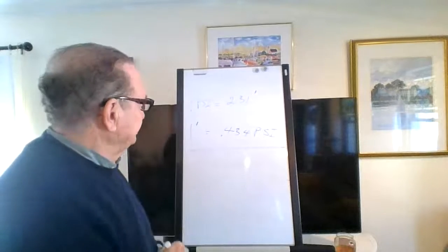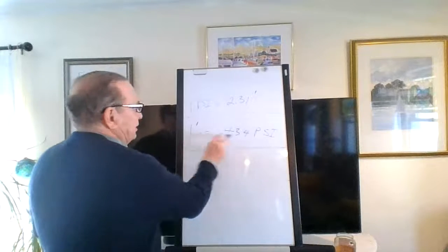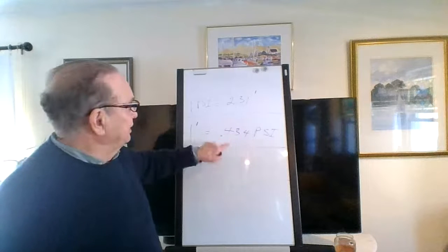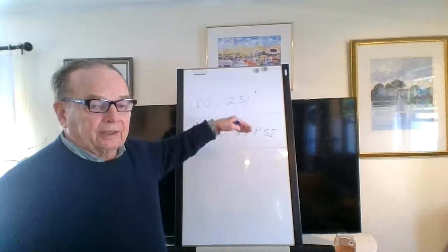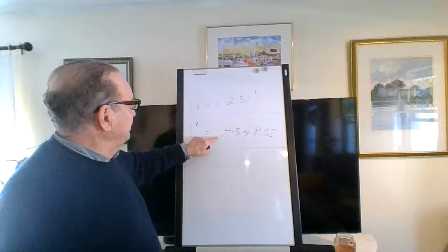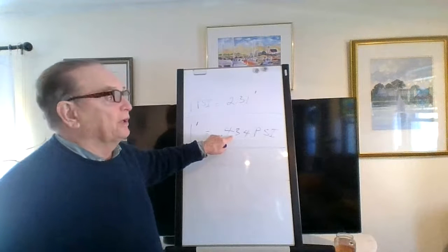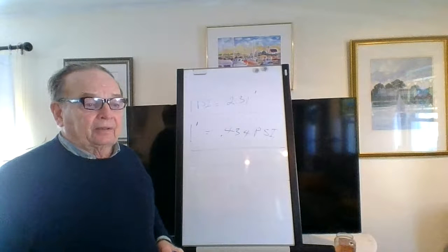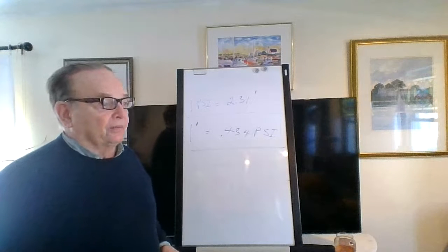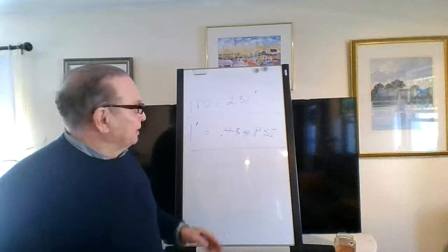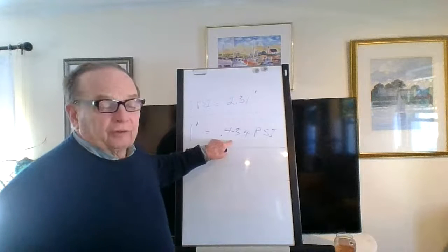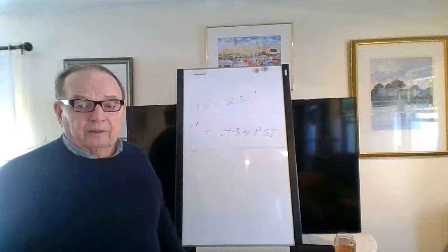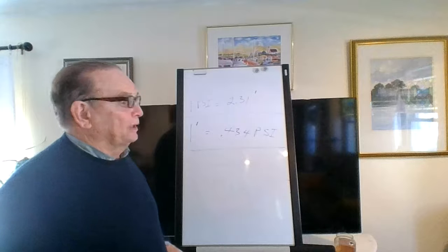Well, let's check. Every foot is 0.434. So we go up a foot, 0.434. We go up 2 feet, 0.868, and so on. For a 10-foot head of water, you just move the decimal, like you do when you underground test your cast iron or your PVC, if it's residential. It puts a pressure of 4.34 pounds on the system. So 4.34 pounds per square inch.